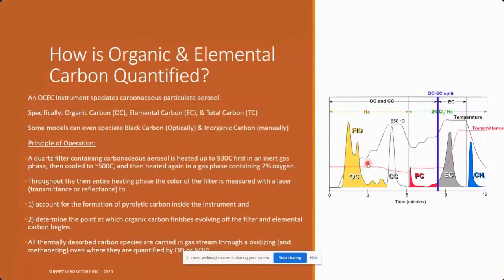So once the instrument has fully completed the heating process, we then run what we call our calibration peak, where we inject an internal standard into every analysis. This is a very useful way to quantify the unknown detector signal. The instrument is installed with a calibration gas, and so every single analysis will actually have this internal standard.